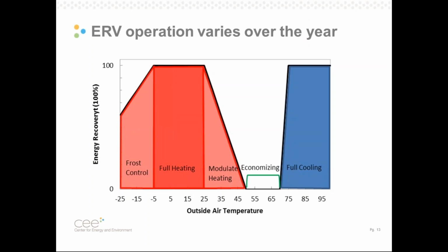This is where it now works in conjunction with a heating system. In this case, this is the prime heating season in Minnesota from around -5 to 25 degrees. Energy recovery acts as the first stage. It preconditions the outside air. The heating system brings it up to discharge air temperature.